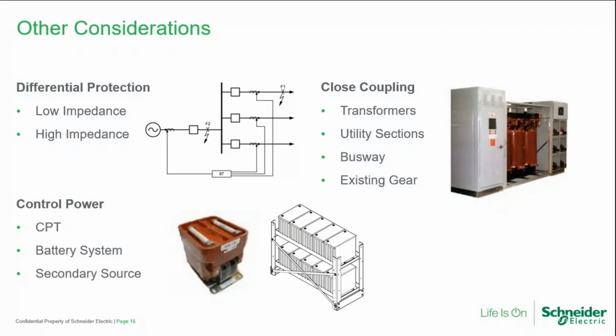I had a couple more questions I'm going to run through real quick. With Rogowski coil CTs, I'll go back to the top. Why aren't voltage dividers used in metal clad? I've actually seen some designs where they are being used in metal clad. I think that's newer to the market, but I think you'll see more and more of that. What is the time frame for SF6 to be tested? I'm not quite sure. SF6 is already on the market today, and as I showed you before, there's a new standard coming out in which it'll lay out production testing and design testing, but it'll be very similar to the metal enclosed. So SF6 is available today already on the market.